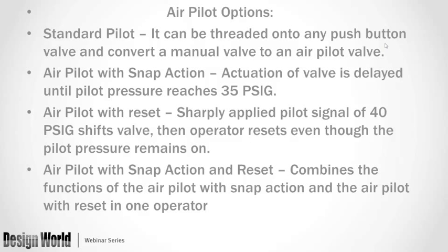They have air pilots with snap actions. Actuation of the valve is delayed until the pilot pressure reaches 35 psi. Air pilots with reset: sharply applied pilot signals of 40 psig, that's gauge pressure, shift the valves, and then the operator resets even though the air pilot remains on. And the last one, they have some air pilots with snap action and reset, which combines the function of the air pilot with the snap action and the air pilot with reset in one operator. Okay.